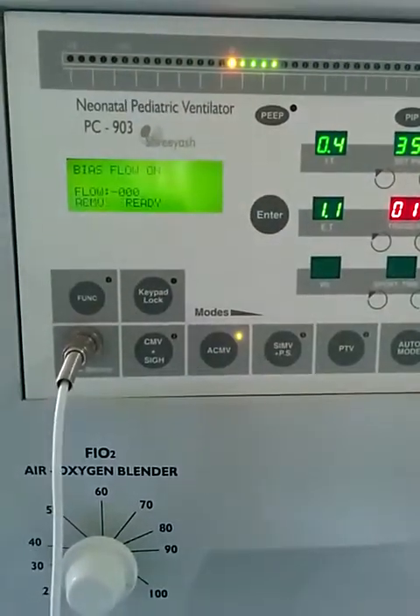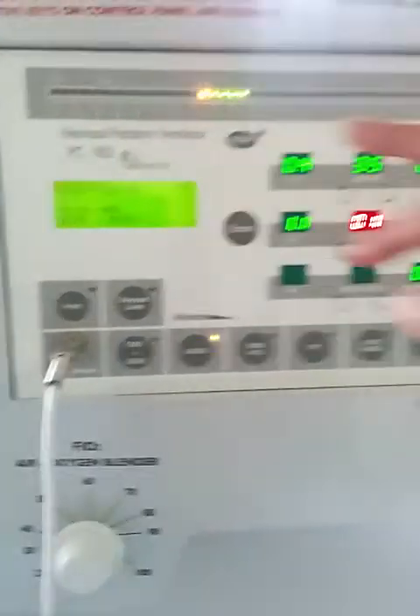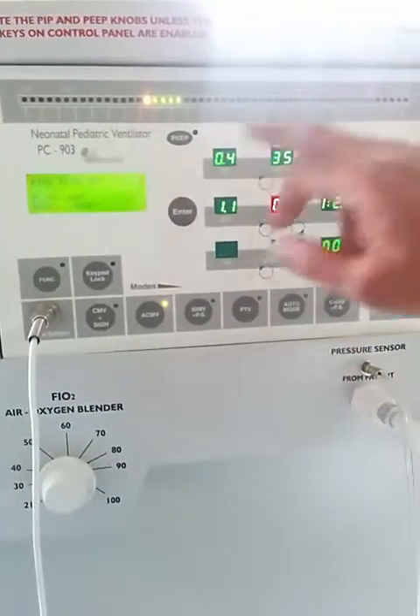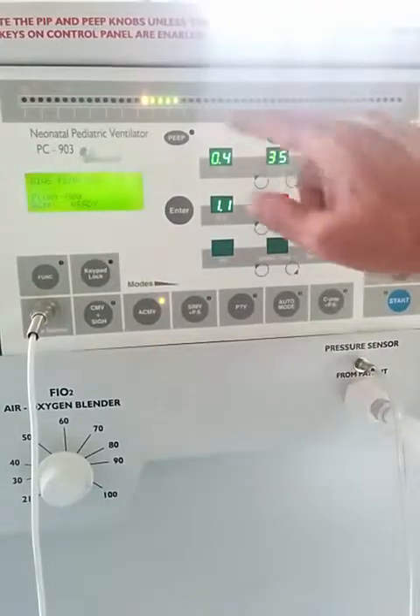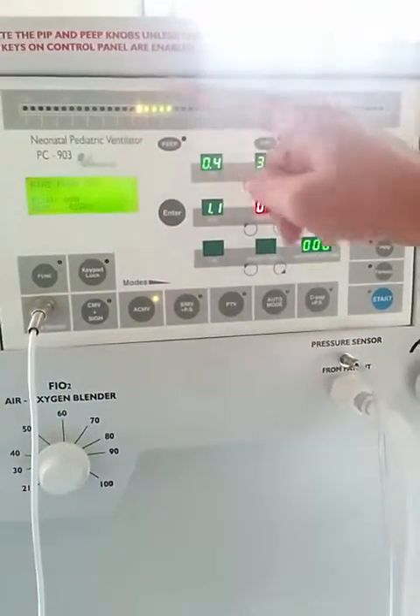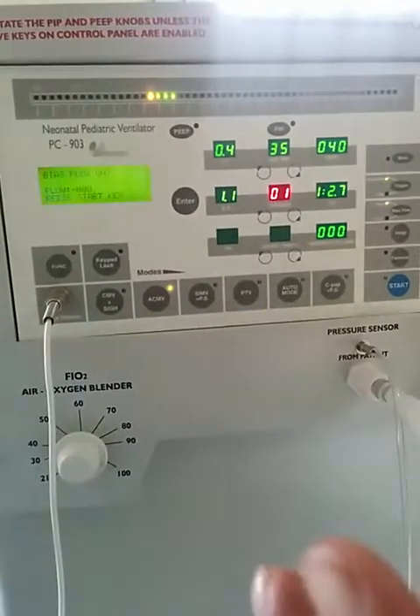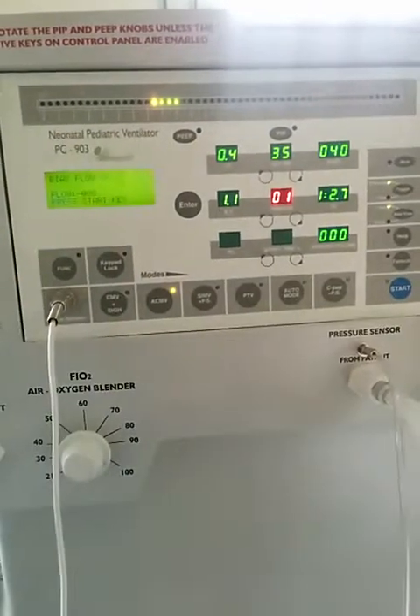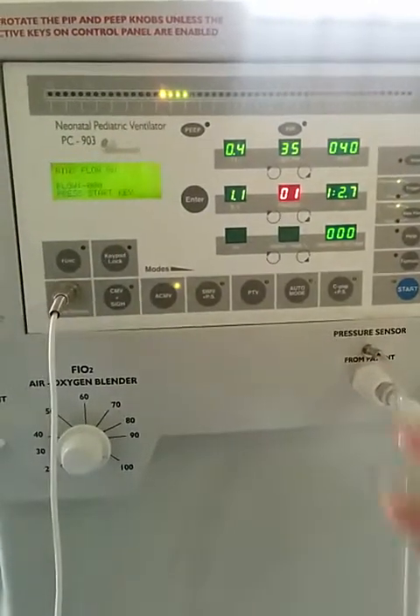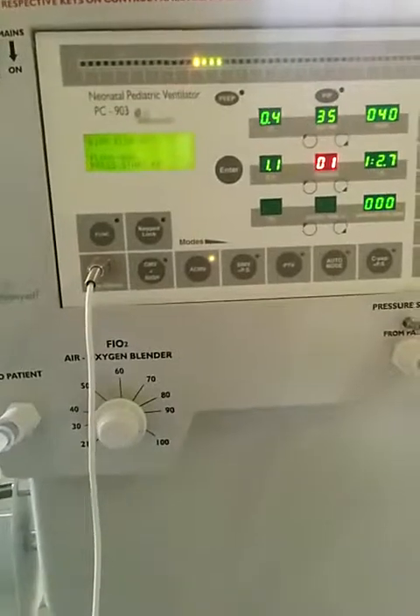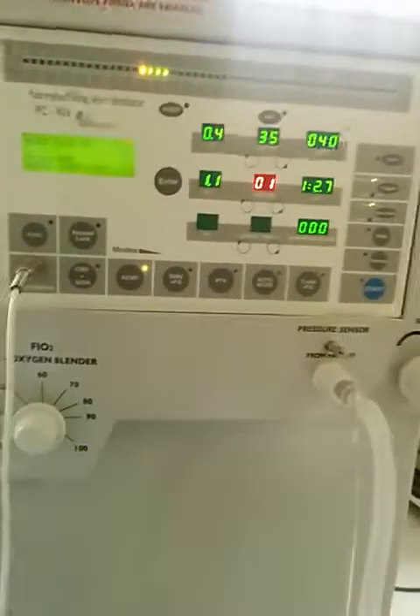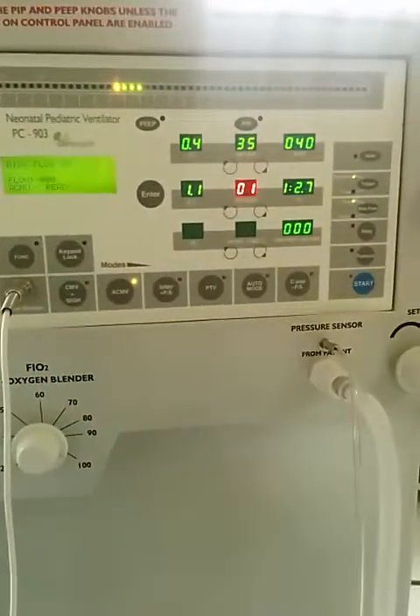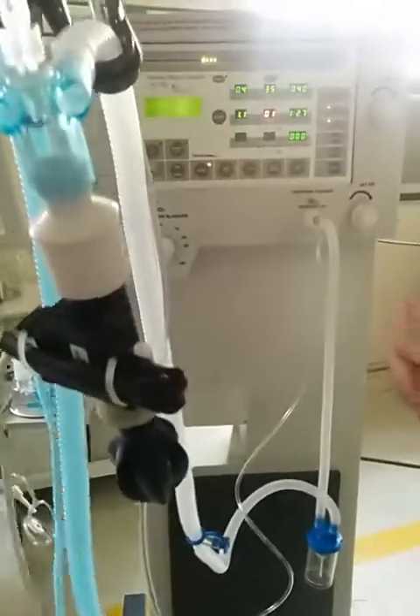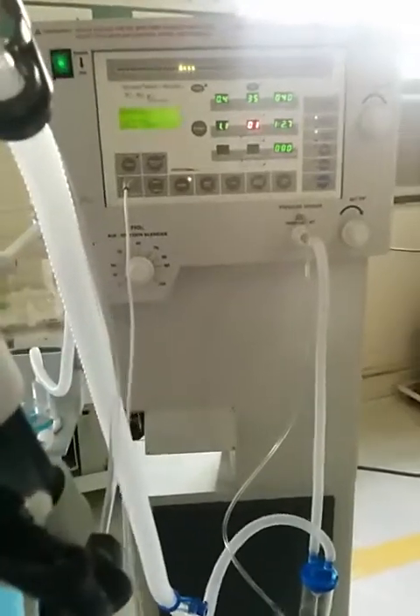Press start. So now what we have set is the inspiration time, the respiratory rate, and the PEEP. We have not set the inspiratory pause, nor the sigh breath. What remains is that we have still not set the peak inspiratory pressure. Before connecting the ventilator to the baby, you always use a test lung for setting the peak inspiratory pressure, that is PIP.